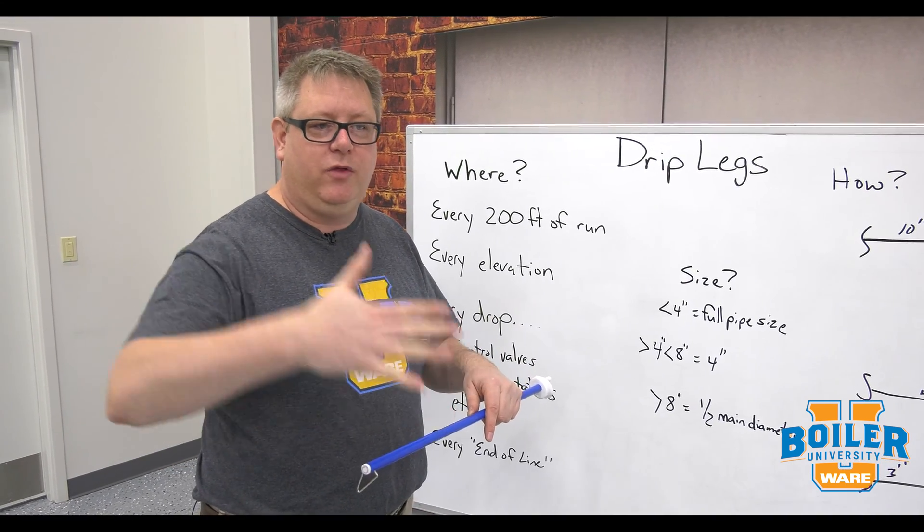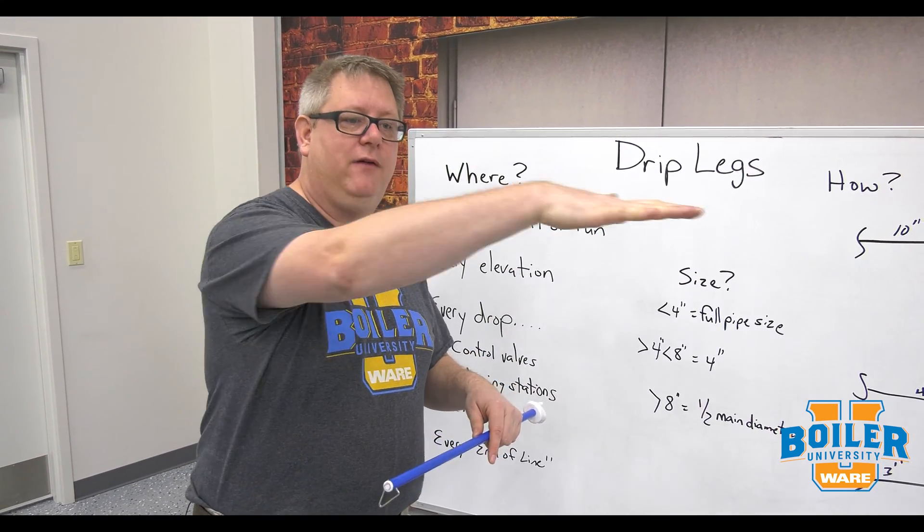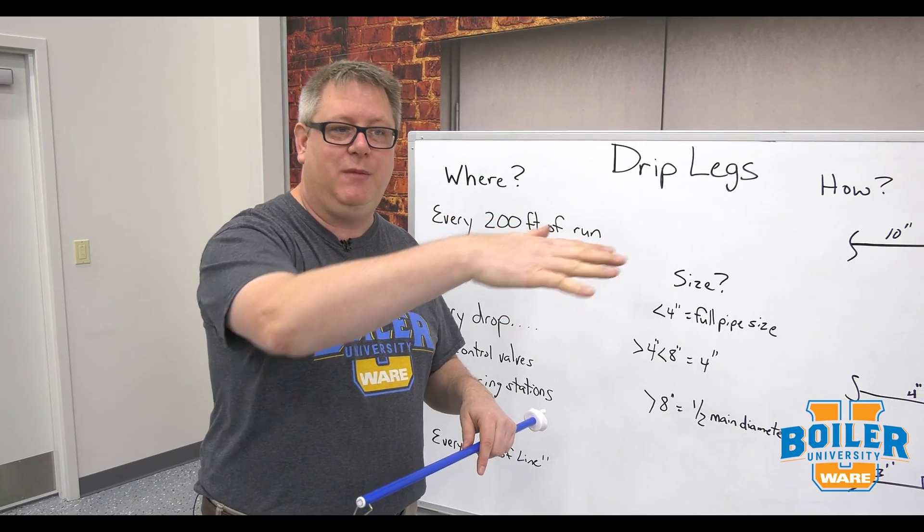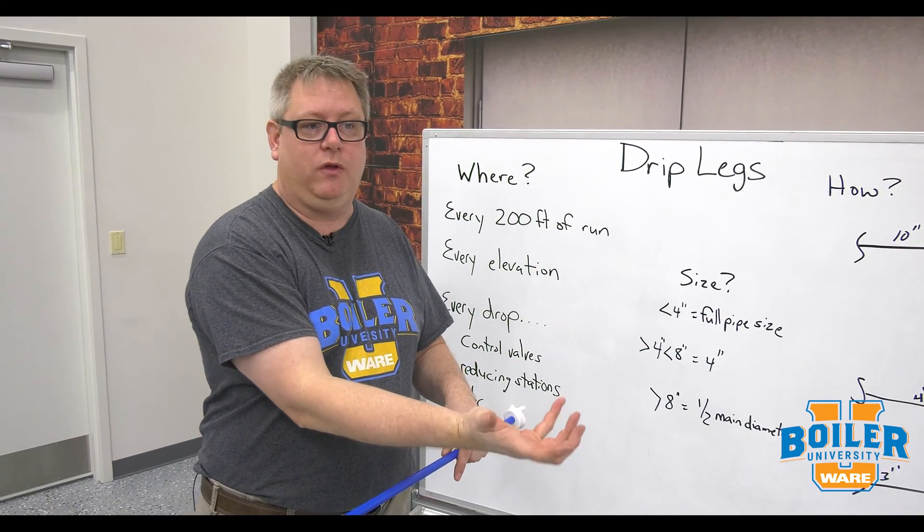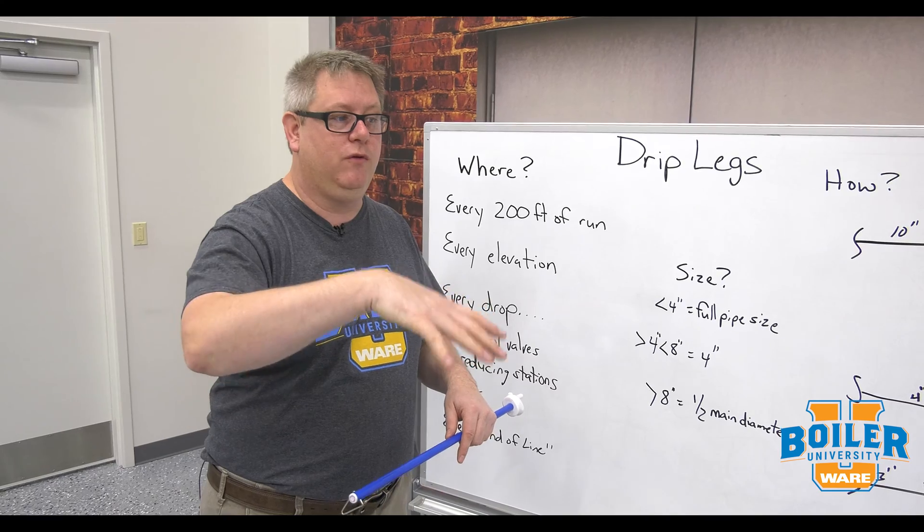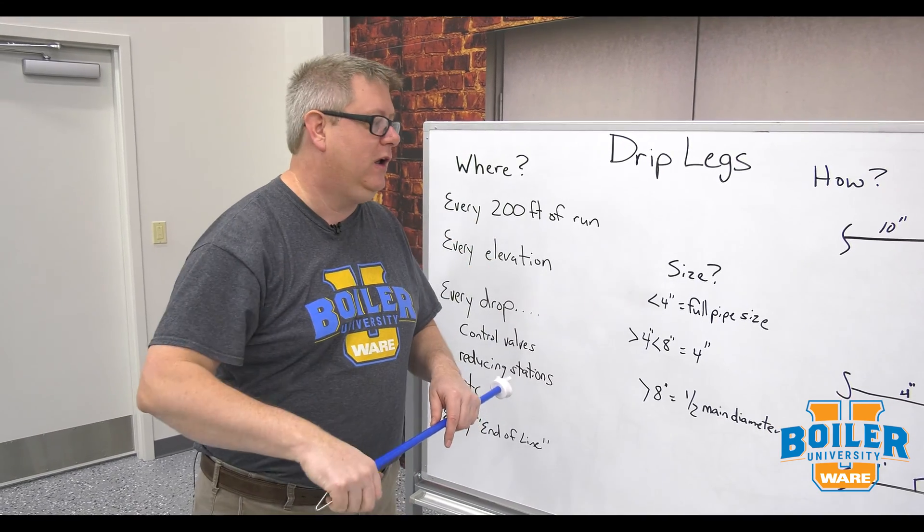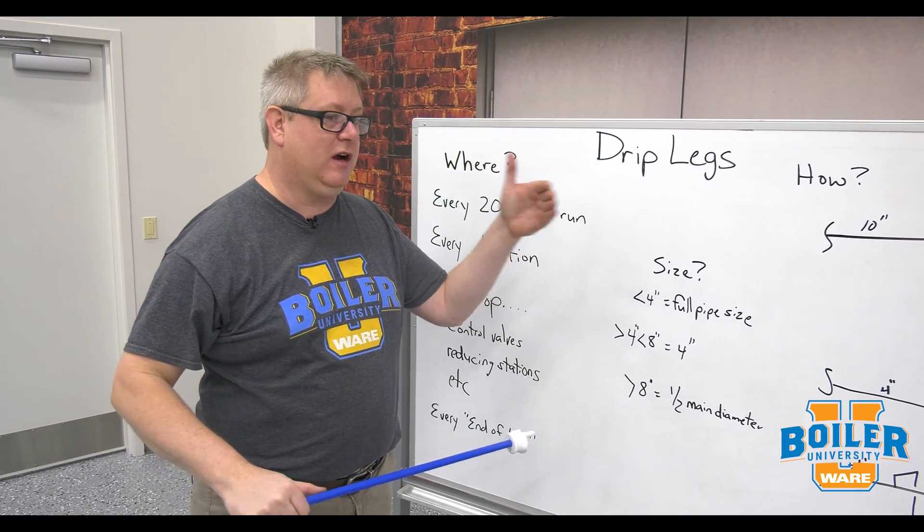And the problem is with the velocity and smearing of the condensate down that pipe, it's not going to go into that weld-o-let. A weld-o-let will only remove literal standing water in the pipe, and that's not accomplishing our goals.